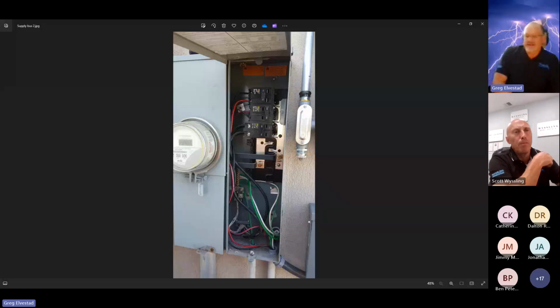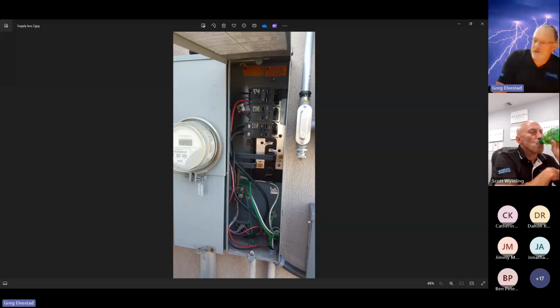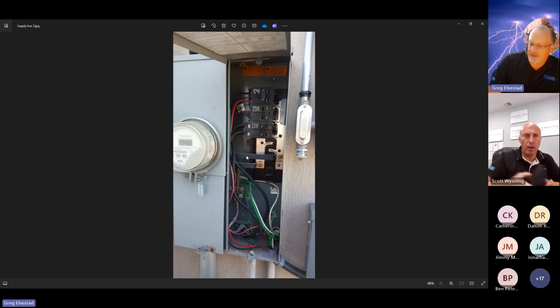So supply side means that there's nothing to turn off the power that you're connecting onto, the power connecting conductors between the meter and the home. So for example, on this screen here, you'll see there's a meter here on the left, and you've got some circuit breakers up in this area at the top. But the crucial part is right here in the middle of the screen. You see these black bars bolted to the bus bar here, the power distribution bus bar. This is the supply spot.